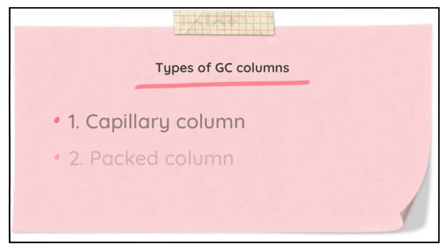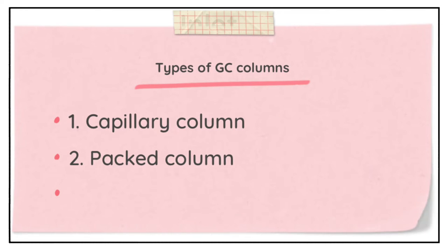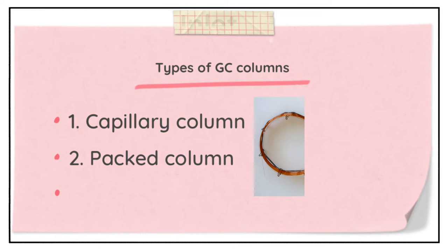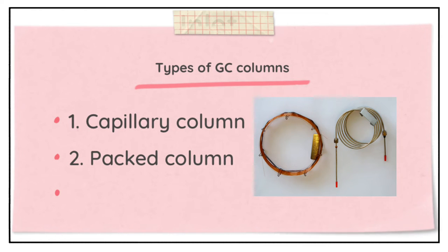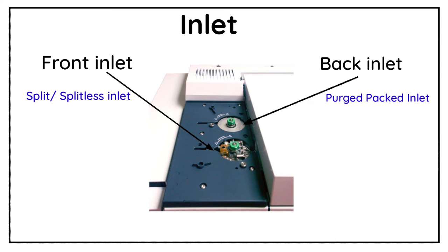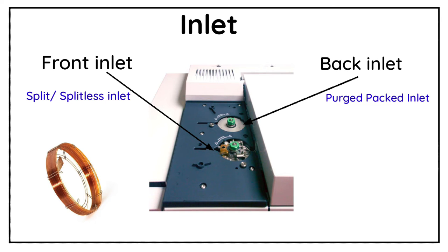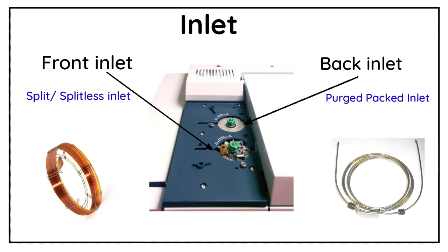The reason for having two inlets is that there are two types of GC columns — one is the capillary column and the second is the packed column. Whenever a capillary column is required for analysis, the split/splitless inlet will be used, and when the packed column is required for analysis, the purged packed inlet will be used. I hope you have understood the difference between the two types of inlets.